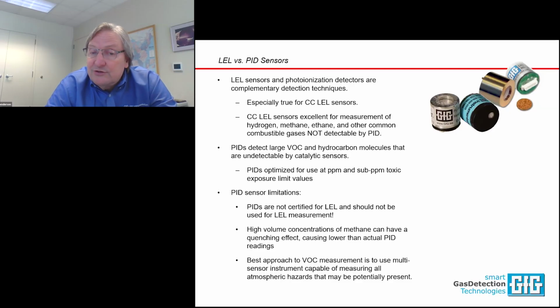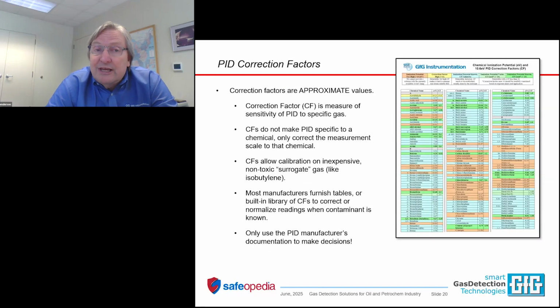PID sensor limitations: PIDs are not certified for LEL measurement and should not be used for LEL measurement. If you need an LEL reading, make sure you have an appropriate LEL sensor. The best approach in a multi-sensor instrument is to have both an LEL sensor and a PID sensor in the same instrument, and any other sensors that you might need to measure specific gases of interest.